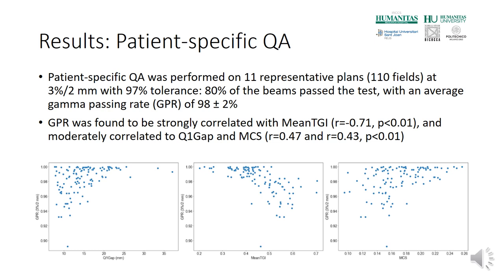To investigate potential correlations between the complexity metrics and the patient-specific quality assurance results, we performed patient-specific QA on 11 representative plans, i.e. 110 fields, at 3% 2mm with 97% tolerance. We found an average gamma passing rate of 98 ± 2% with 80% of beams passing the tests. Furthermore, we found that the gamma passing rate was strongly or moderately correlated to the analyzed complexity metrics.